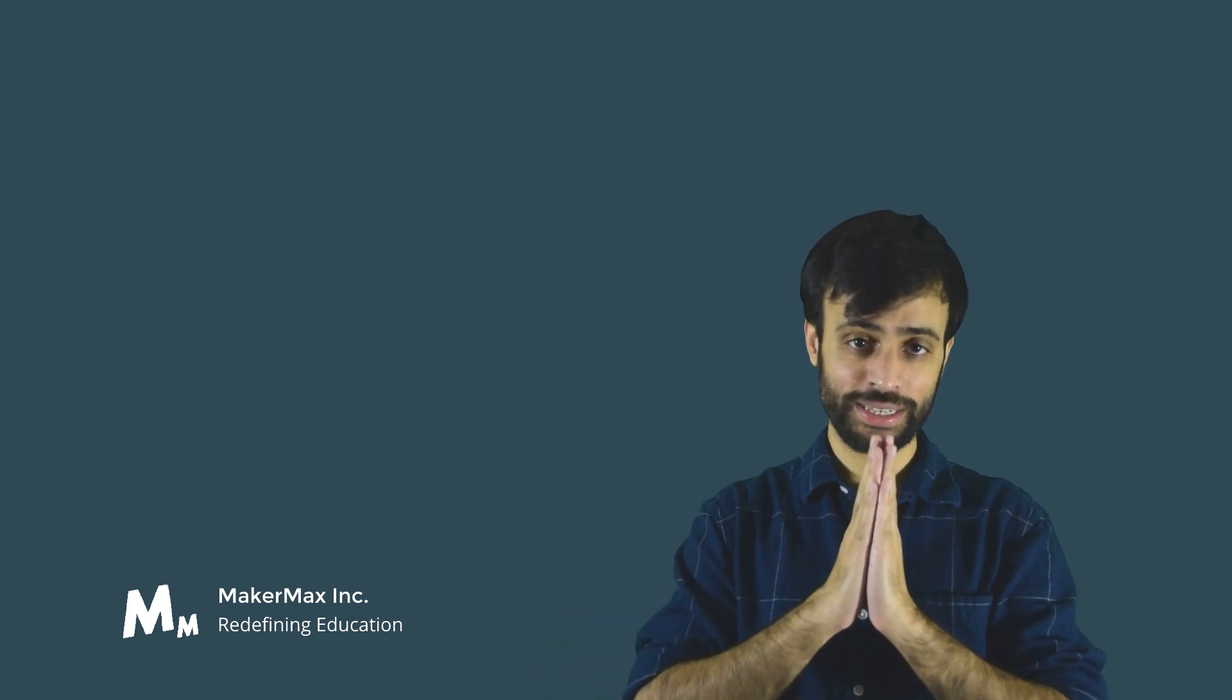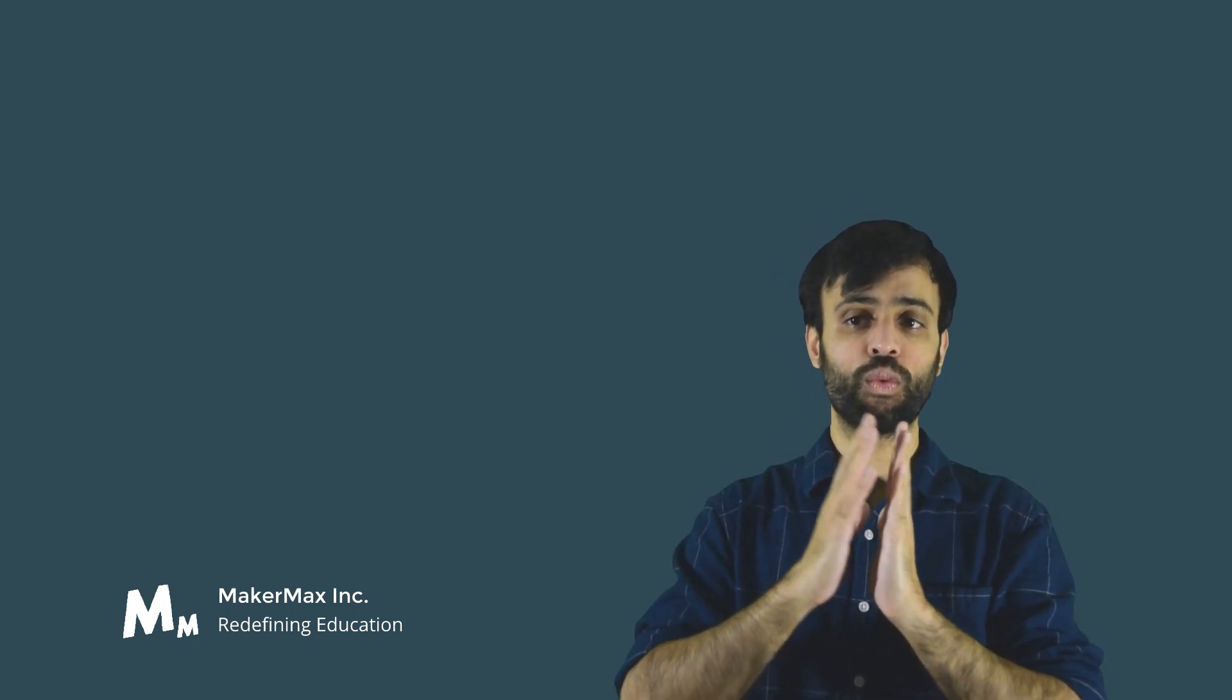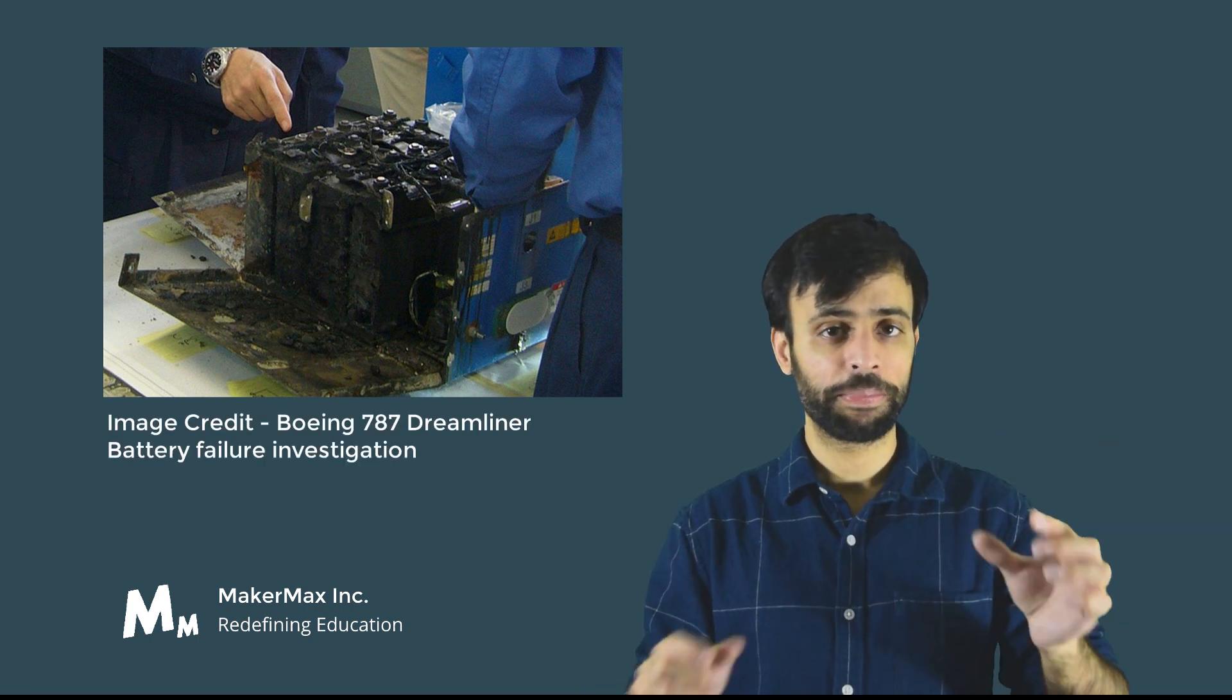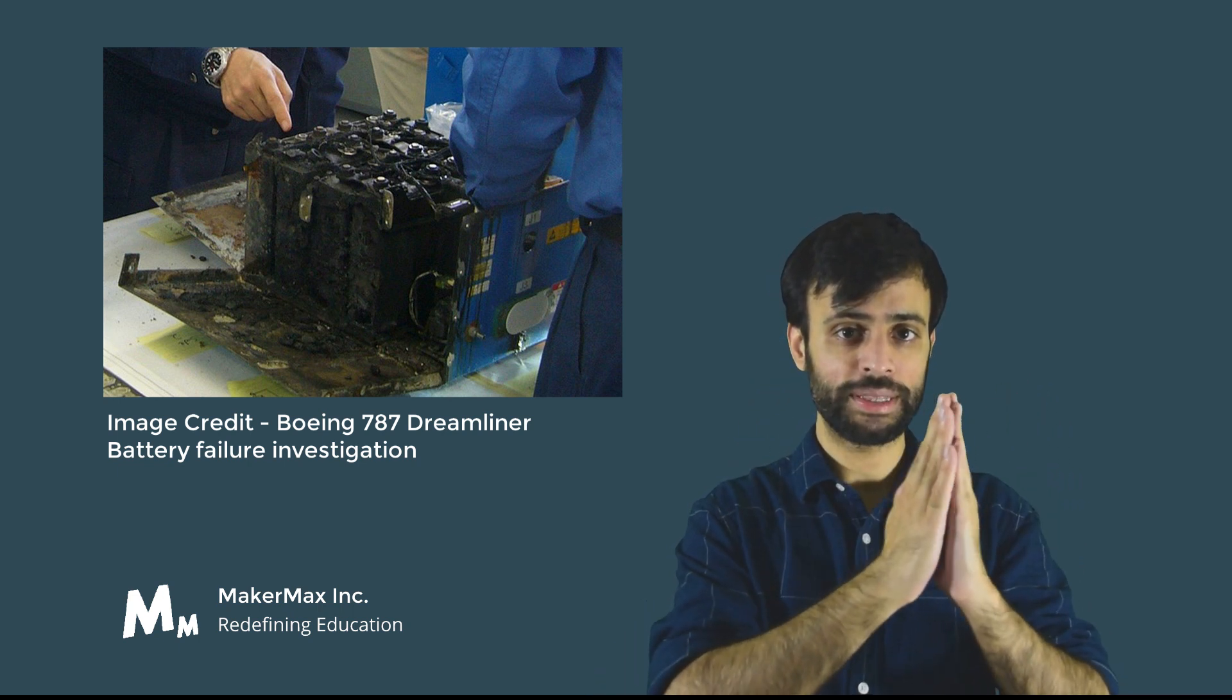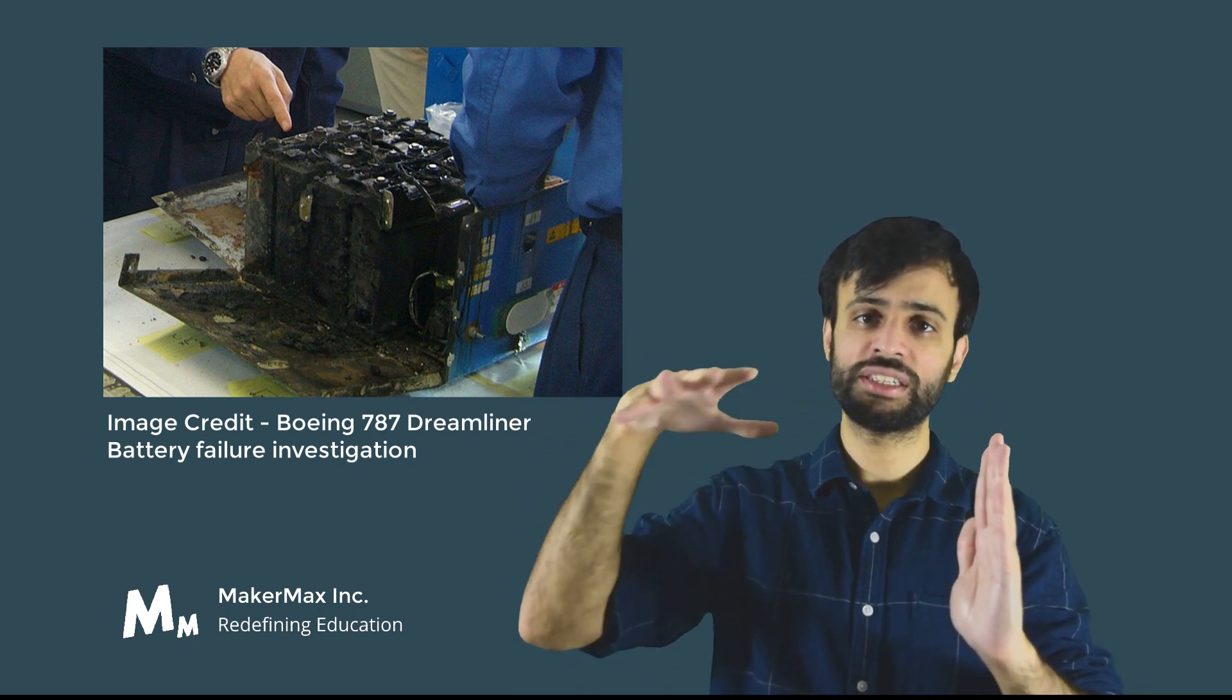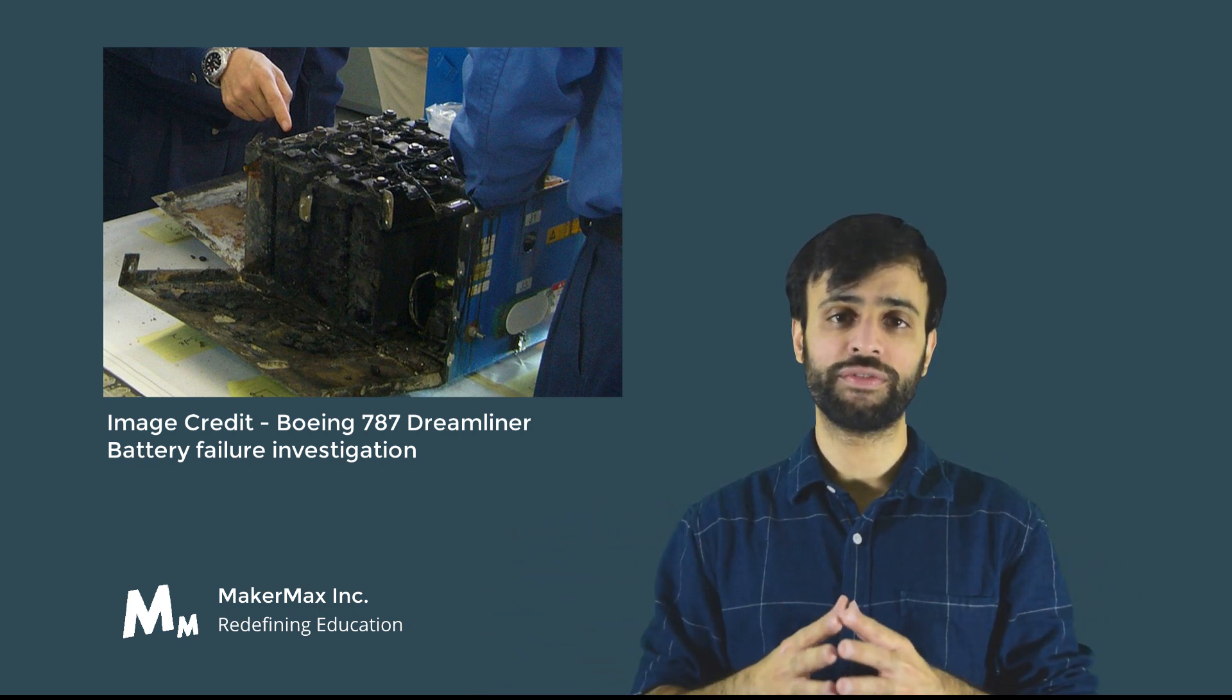This is why it's important to understand thermal runaway procedures in a single cell, as well as understand what happens if the battery pack is not designed properly. If you could have just isolated a single failure in a cell and stopped the failure in that isolated corner, but instead, because of poor pack design, adjacent cells have also gone into thermal runaway, the propagation of that failure will really cause a lot of devastation.